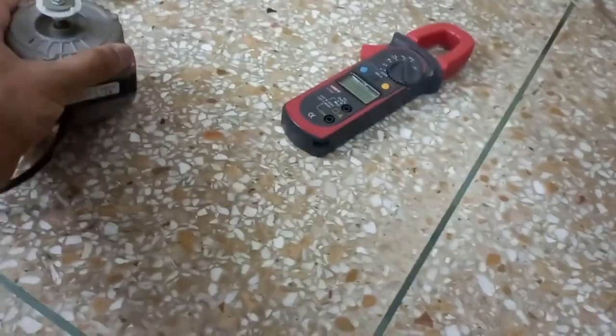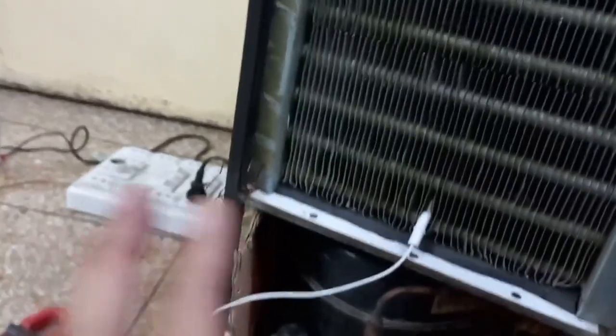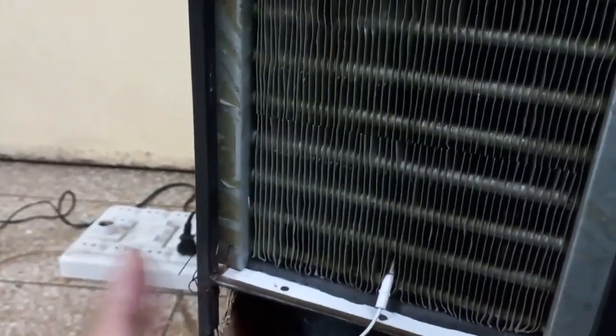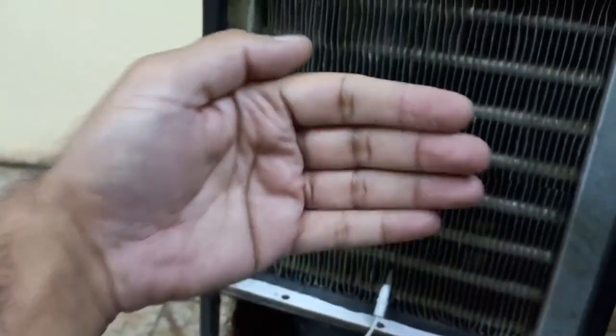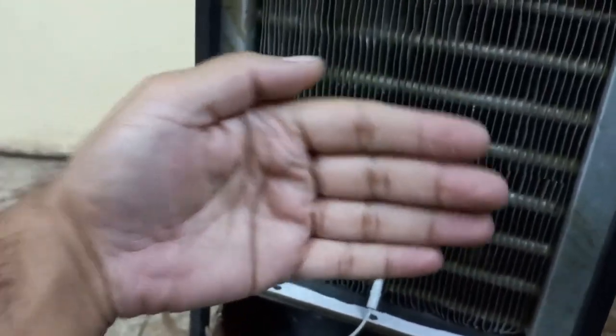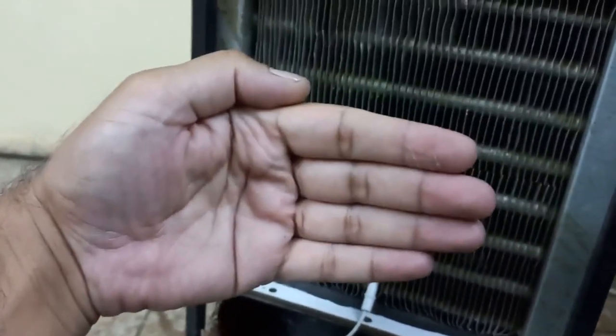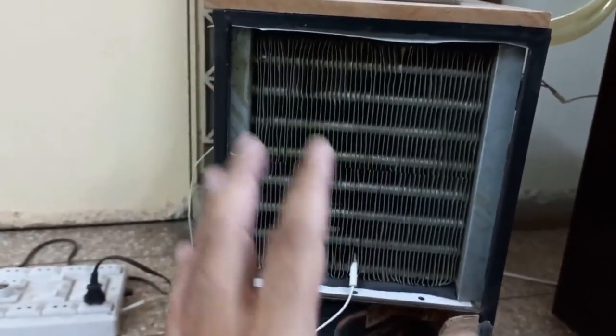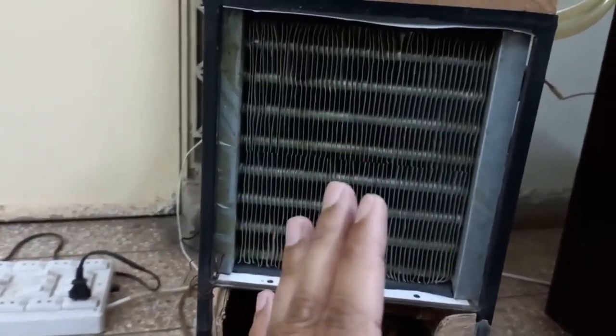So to reduce the current, I used this one. But today when the ambient temperature increased, I observed the condenser is not too cool. And when the condenser is hot, then the compressor will be hot, and the complete system efficiency will be less. Now I am putting my hand here and hot air is coming, but that air is not as hot as before. After connecting this big motor, I still observed that velocity had not increased, air was the same as before.